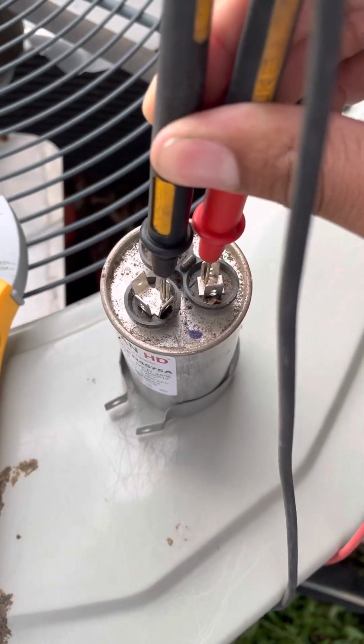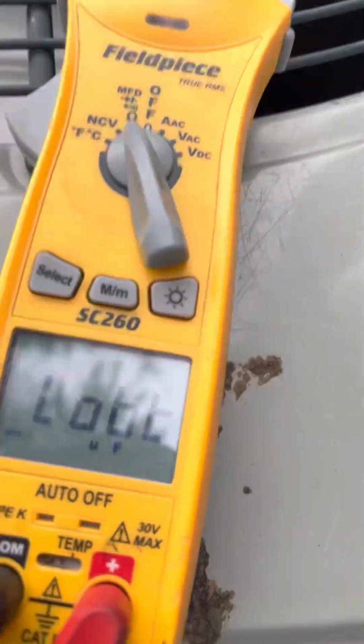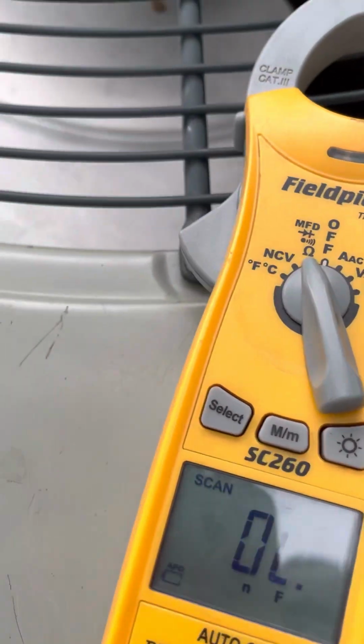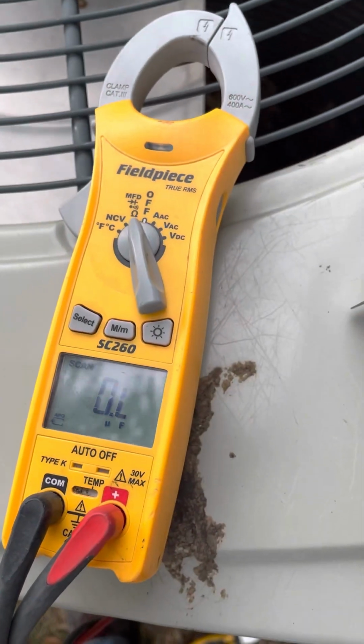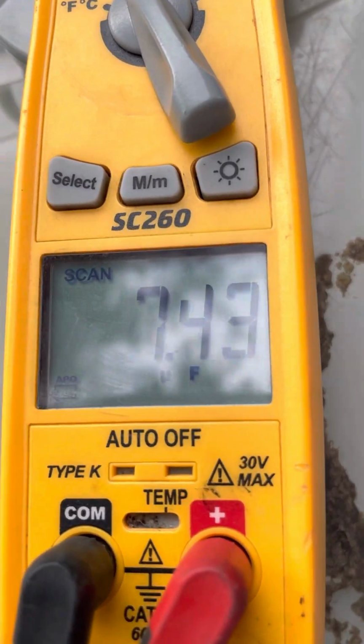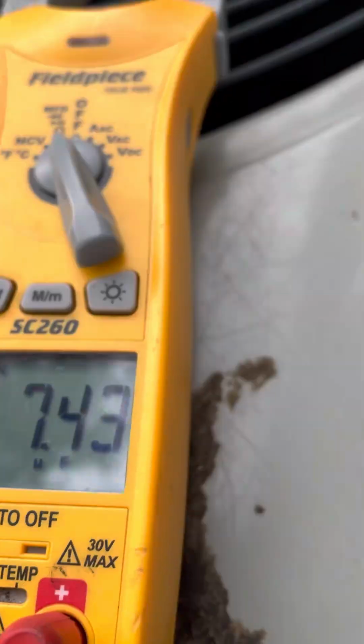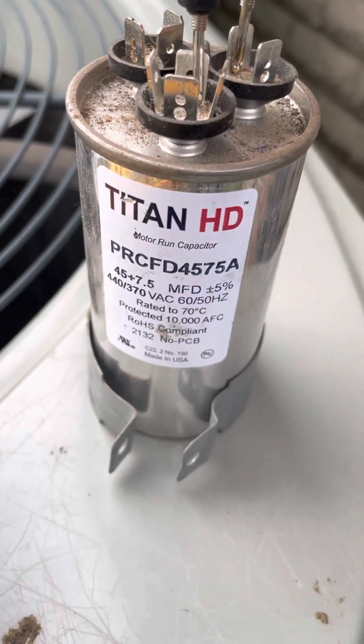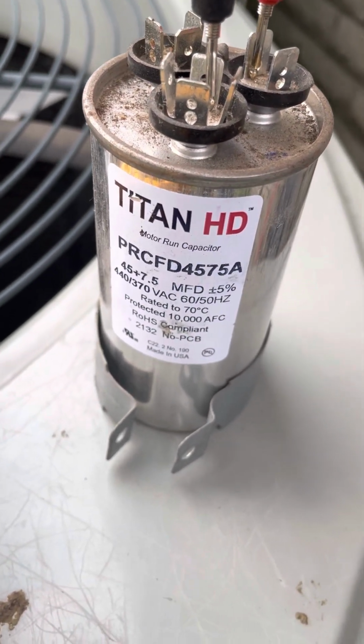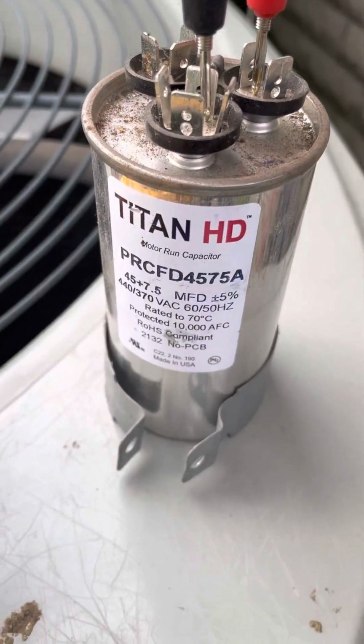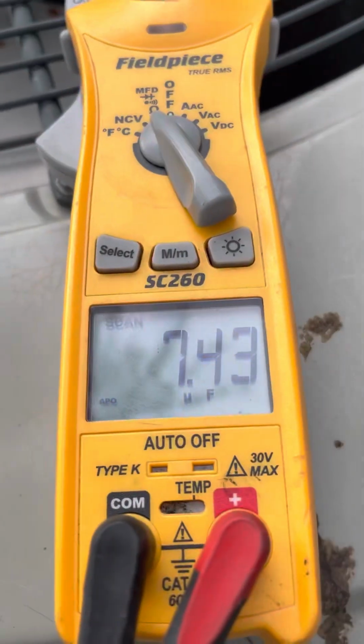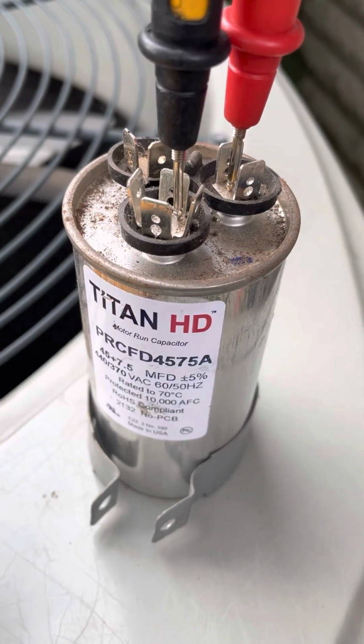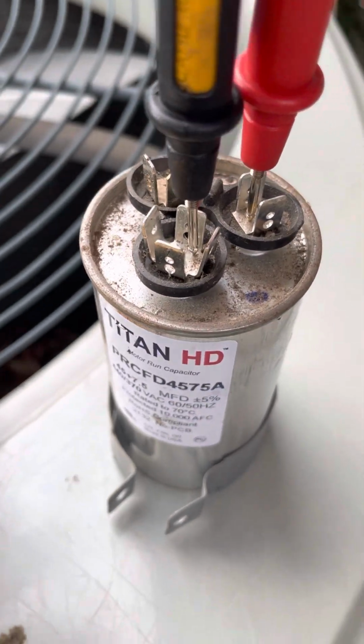Let me just reset this. Sorry, I need to change the battery for my meter. All right, so as you can see, we're at 7.4. We are rated for 7.5, so we're not exactly at 7.5, but we are within that 5% range. So this capacitor for the fan is good. Let's go ahead and check it for the compressor.